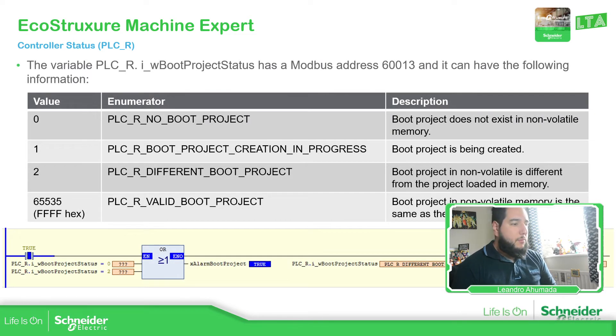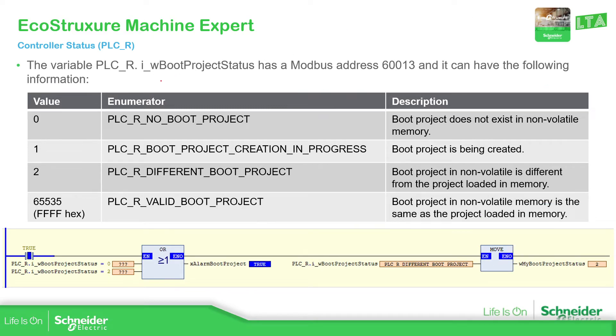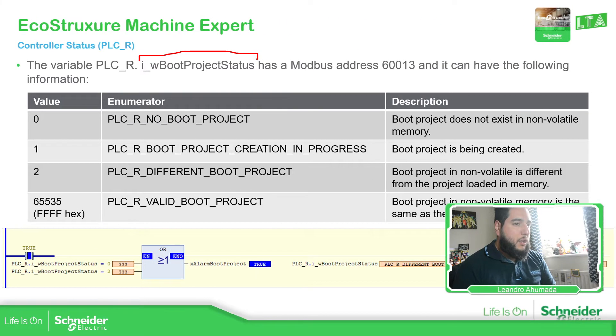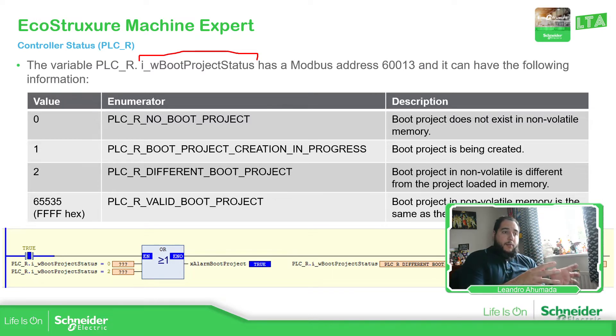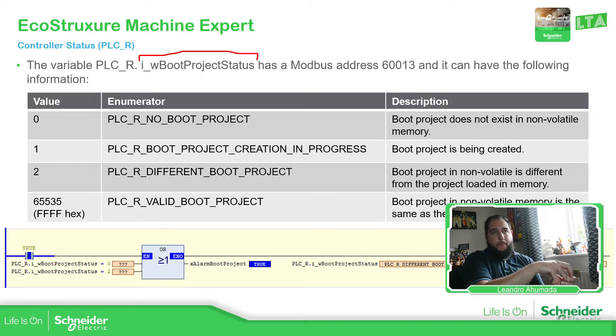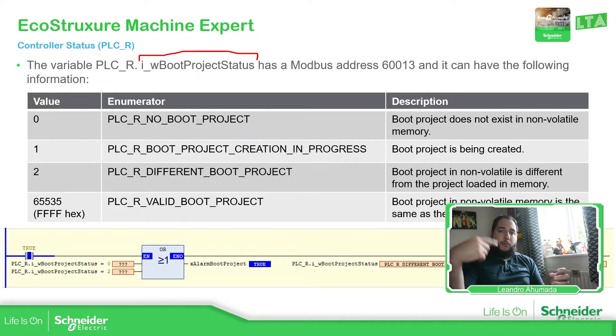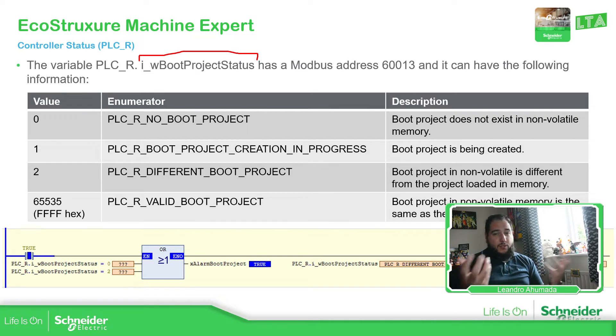Another variable that we have is the status of the boot project. So basically the boot — how to explain this part. In the controller, we have a volatile and non-volatile area. In the non-volatile area, our boot project is going to be stored. So when the PLC boots up, it moves or copies the boot project to the volatile area. The volatile area is the one that runs the program. So if we don't have this boot project, the PLC doesn't have anything to run — there is no program.